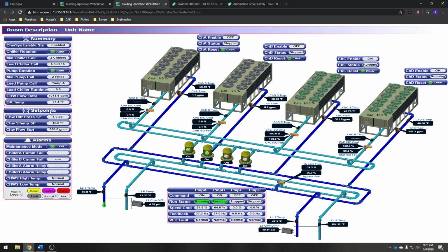So 5, that's the number. We know that because that is what's over here. This is the set point. These pumps will again modulate up and down to maintain that differential pressure. See, we just saw it drop to 3.3. These will start spinning up to get back to the right speed.